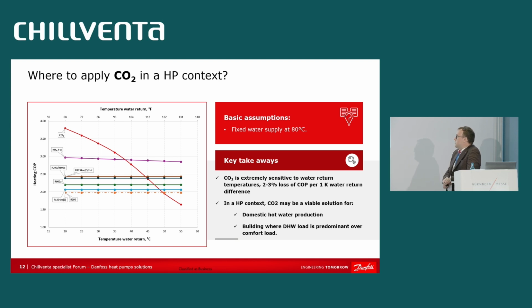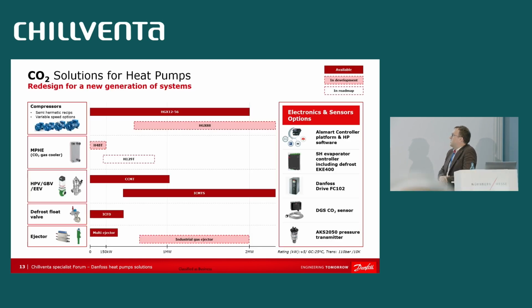In a heat pump context, CO2 makes a lot of sense for domestic hot water production, or in a building where you have a huge load of domestic hot water versus the need of comfort, so that you are able to operate with a water return temperature that is below 40 degrees. For sure, when you have a building that is only for underfloor heating, CO2 makes no sense. And for radiators, it starts to be already quite a challenge if the conditions are not met. So that's really where we are pushing our CO2 solution in the heat pump context. Really hot water production could also be industrial cases.